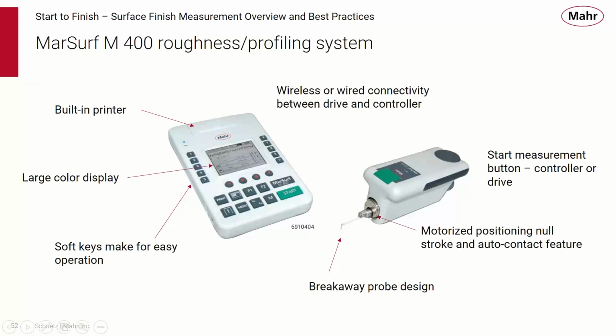And also with the M400, the motorized positioning allows the user to position the probe above the part, actually not touching it. And when the measurement process starts, the drive will move down, sense that it's touched the part, and then begin driving the probe to make its measurement. So again, less chances of damaging probes. And this is one of the most common problems with a lot of the competitive instruments.